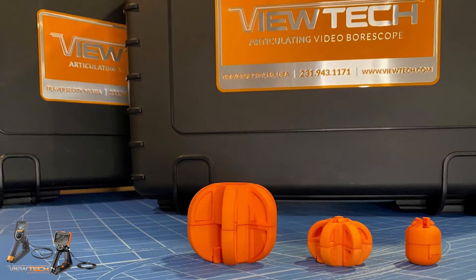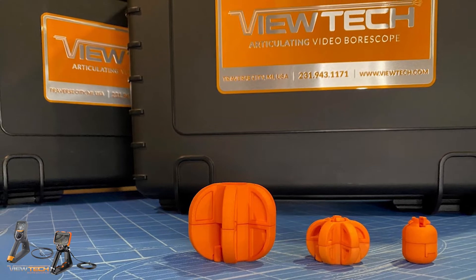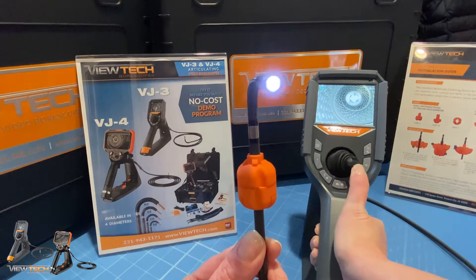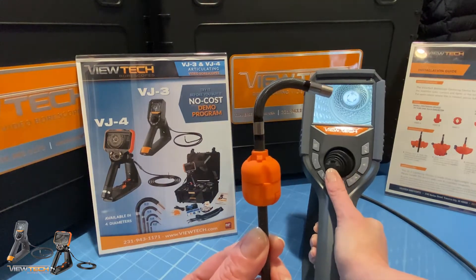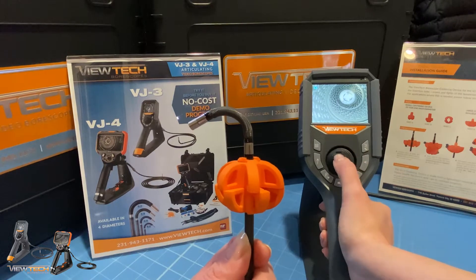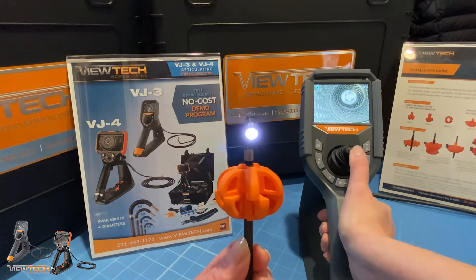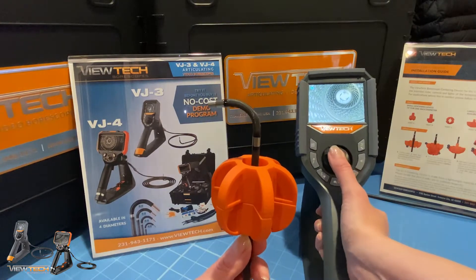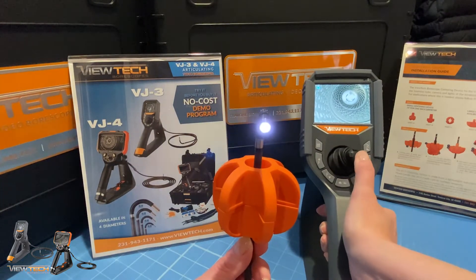ViewTech borescope centering devices are available in three different sizes. First, a three-quarter inch centering device, optimum for piping at least an inch in diameter. Next, a one and three-quarter inch centering device, optimum for piping at least two inches in diameter. And finally, a two and three-quarter inch centering device, optimum for piping at least three inches in diameter.